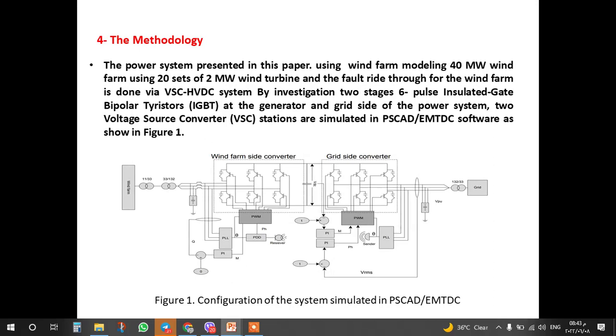The methodology of this research is the power system presented in this paper using wind farm modeling: a 40 megawatt wind farm using 20 sets of 2 megawatt wind turbines, and the fault ride-through for the wind farm is done via the voltage source converter high voltage DC system. By investigation of a 6-pulse stage in insulated gate bipolar transistors, IGBT, at the generator and the grid side of the power system, two voltage source converter stations are simulated in PSCAD software as shown in this figure.